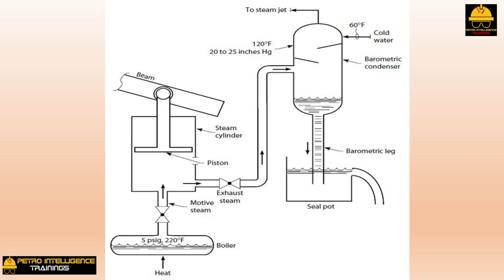Two problems arose with the use of the barometric condenser. First, if the condenser operated at sub-atmospheric pressure, how can the water be drained out? The solution: set the condenser on a hill 34 feet high, then drain the water down through a barometric leg to a seal pot. The pressure that a column of water 34 feet high exerts is equal to one atmosphere, hence the term 'barometric leg.' The second problem was air leaks — air drawn into the system would build up in the condenser, and this non-condensable vapor was drawn off using a steam jet.